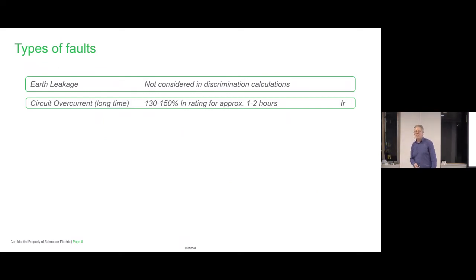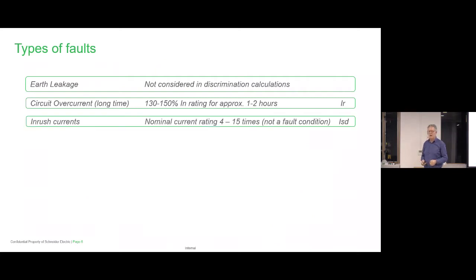Circuit overcurrent fault, long time. This is your typical one, the major fault that you see out in the field. It's 130 to 150%, could be less than that, but it's going to be around that 1.3. You might have heard that in the standard, 1.3 times. It can take up to 1 to 2 hours on some of these protection devices before they trip, but they're in the tripping zone at that point. And we as a company have circuit breakers that will even give you a pre-alarm saying that you're in an overload state. So it's quite good. The technology has moved on a lot in that area.